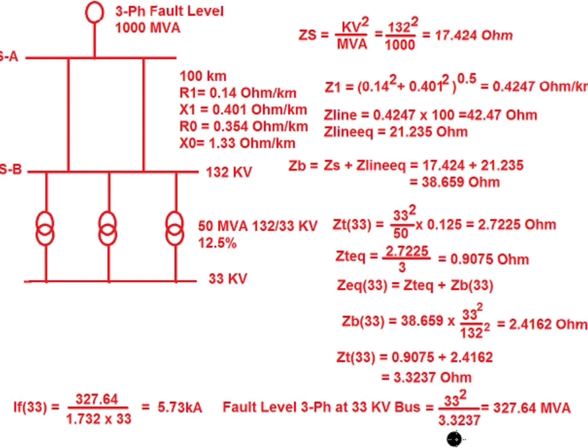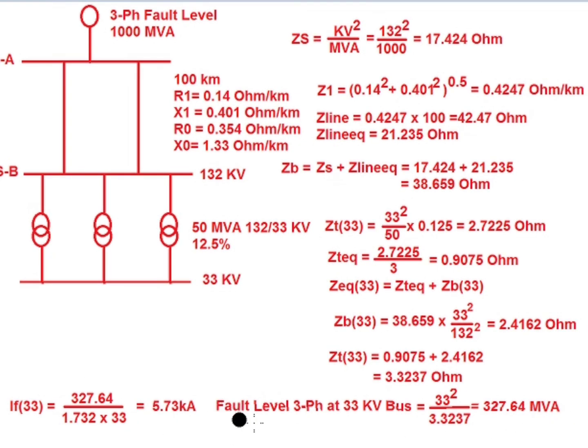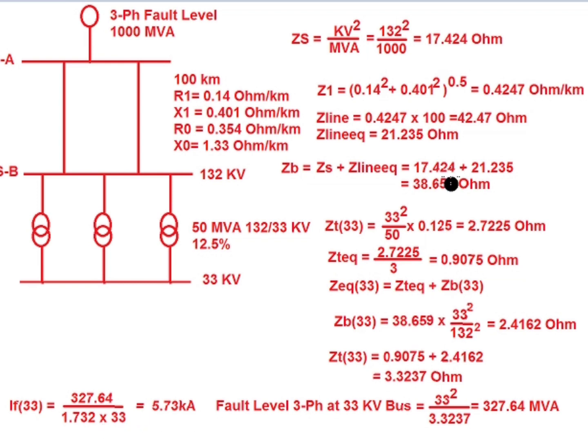The three-phase fault level at the 33 kV bus is: Fault MVA = kV² / Zeq = 33² / 3.3237 = 327.64 MVA. From this, the three-phase fault current at the 33 kV bus is: IF33 = Fault MVA / (√3 × 33) = 5.73 kilo-ampere. This is how we calculate the three-phase symmetrical fault at the 33 kV bus when the fault level at the source substation is known.